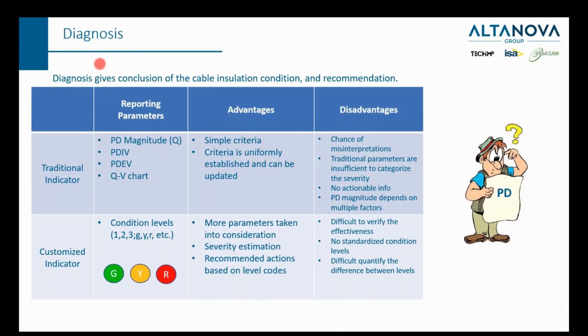Diagnosis, I will not talk too much. Diagnosis is the most important but most challenging part. The traditional diagnostic methods do not give a final conclusion, they just give the numerical measured results. This method is very simple, all the values can be read from the equipment, but it doesn't give the operator information on what we need to do. What does it mean? The customized indicator, like the three-level indicator or some other level indicators, does not directly report the measured parameters like the PD magnitude or other values. It gives red, yellow, green, or level 1, 2, 3, 4, 5, those level systems to evaluate the severity of the insulation condition. And this leveled system will also give actionable items, like what we need to do.